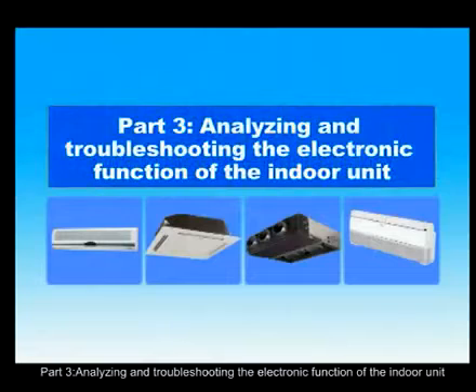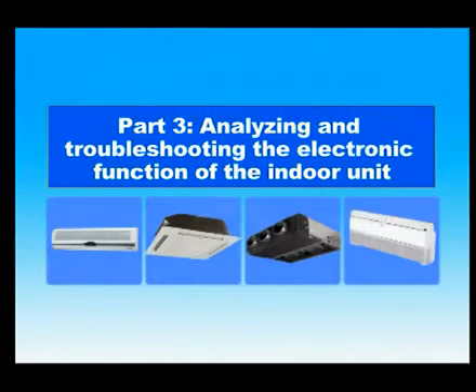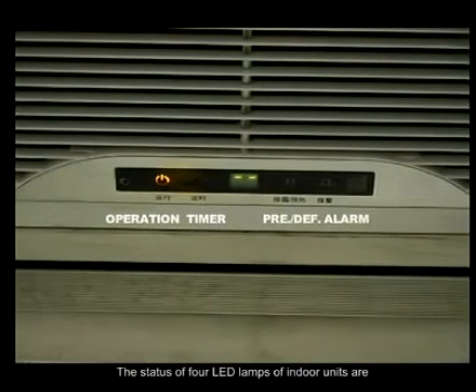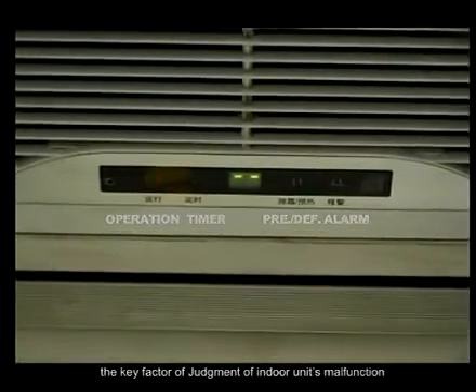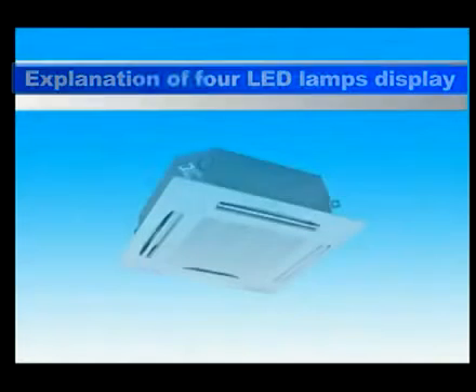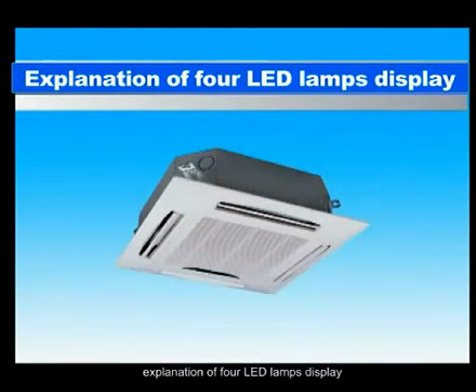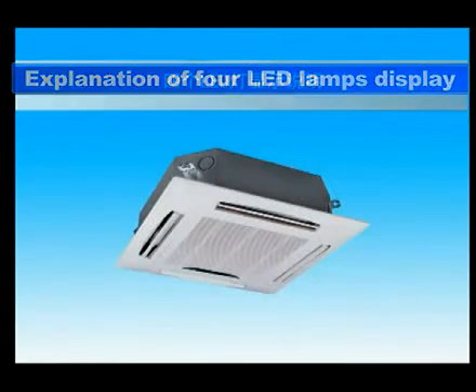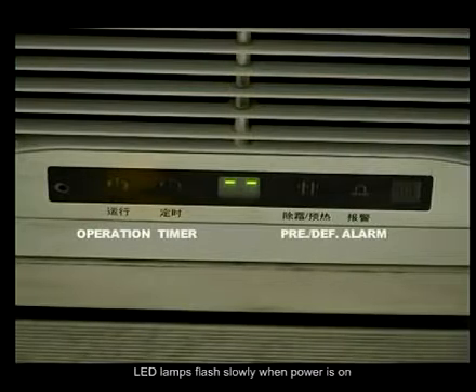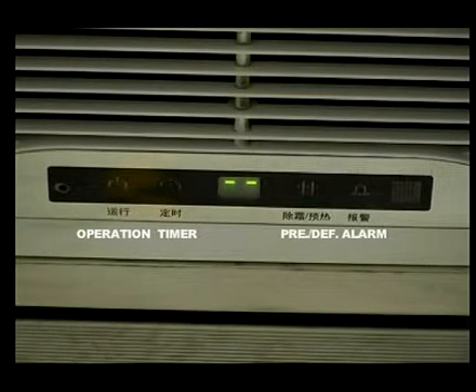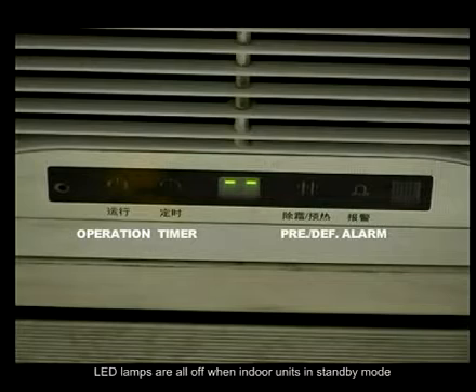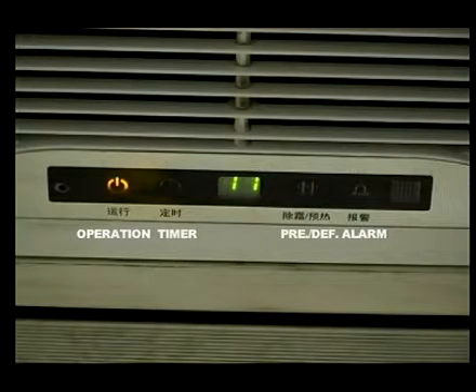Part 3. Analyzing and troubleshooting the electronic function of the indoor unit. The status of the 4 LED lamps of indoor units is the key factor in judging indoor unit malfunction. Explanation of the 4 LED lamps display. LED lamps flash slowly when power is on. LED lamps are all off when indoor units are in standby mode.